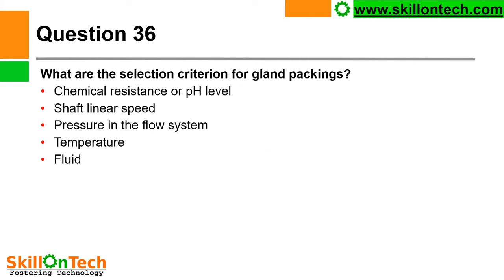What are the selection criteria for gland packings? Chemical resistance or pH level — this is very important because if the media handled by the pump has a low pH, we shall choose the correct gland packing, otherwise it will damage very fast. Also consider shaft linear speed, pressure in the flow system, temperature, and what kind of fluid is handled by the pump. These are some important points for selection of gland packings.